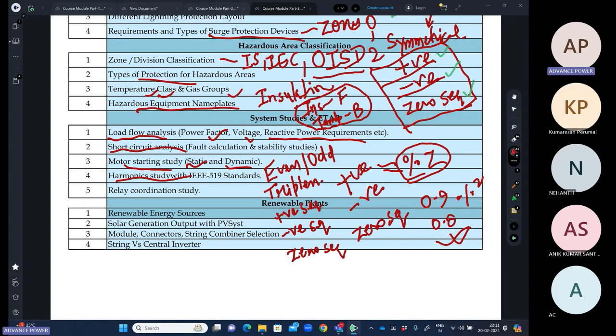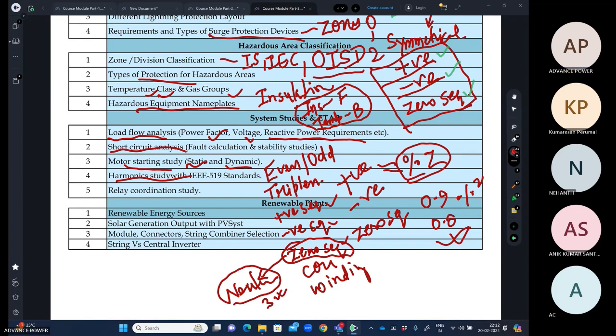So what order of harmonics will be positive sequence, we'll see. What order of harmonics is negative sequence, what order of harmonics is the zero sequence, that we'll see in detail in harmonic classes. And actually what it is affecting, how it is affecting the core of the transformer, how it is affecting the winding of the transformer, how this zero sequence harmonic is affecting the neutral of the transformer. So somewhere we will see the neutral is being oversized, 3 times of the phase rating size also sometimes. So why it is, what harmonics is affecting it, we will discuss in detail.